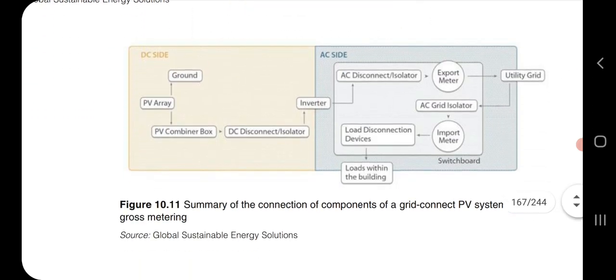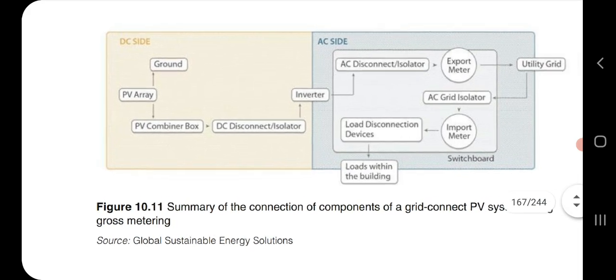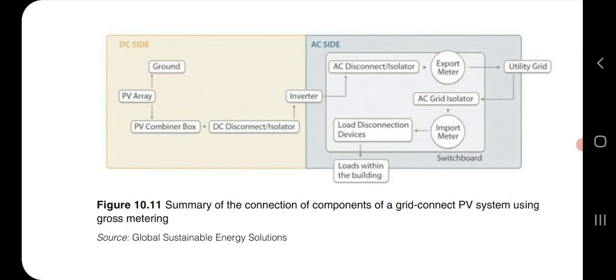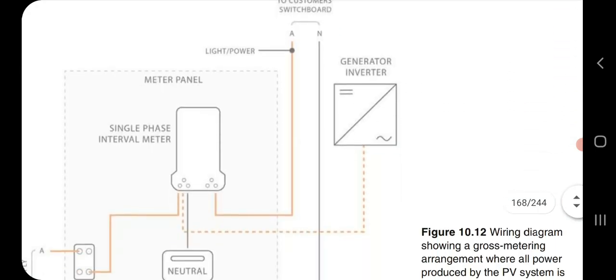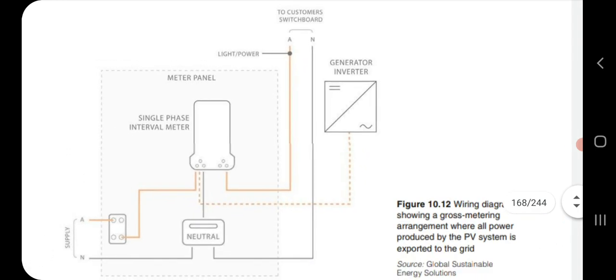This is nothing but a summary of the connection components of the grid using gross metering. This is the gross metering. In the gross metering you can see the ground, PV arrays, combiner box, and you can see it goes to the grid. Export is there, import is there. It goes to the building also, and it goes to the grid system also. For this one the metering section is quite different. In this one they take export and import. So this type of metering is quite different, and they have done a different wiring diagram.